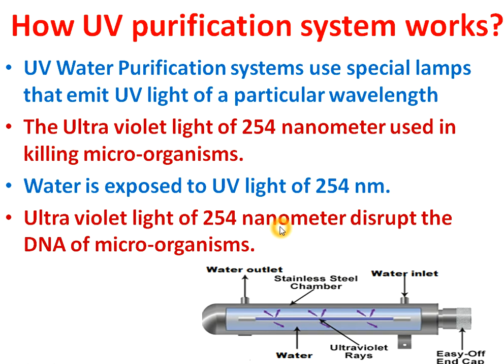In a UV water purification system, special lamps emit UV light of a particular wavelength — specifically 254 nanometers. This 254 nanometer wavelength is very important because if the UV lamp emits more than or less than 254 nanometers, it will not be as effective. Only 254 nanometer ultraviolet light can effectively destroy the DNA of microorganisms.